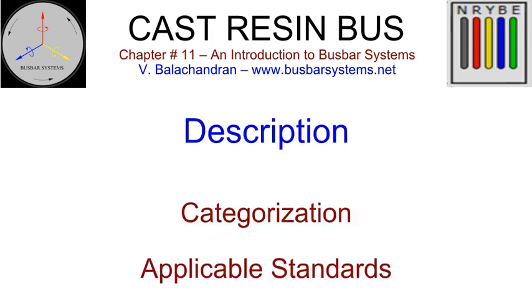Description. Cast resin bus can be broadly categorized based on the service voltage. For application in low voltage, less than 1 kV. For application in medium voltage, more than 1 kV and up to 36 kV. Presently dedicated governing specifications for cast resin bus do not exist either in ANSI/IEEE standards or IEC recommendations. Nevertheless, the following may be used as guiding documents. ANSI/IEEE C37.23 2015 for low and medium voltage bus ducts. IEC 61439 Part 6, year 2012 for low voltage busways. IEC 62271-201, year 2017 for medium voltage bus ducts.